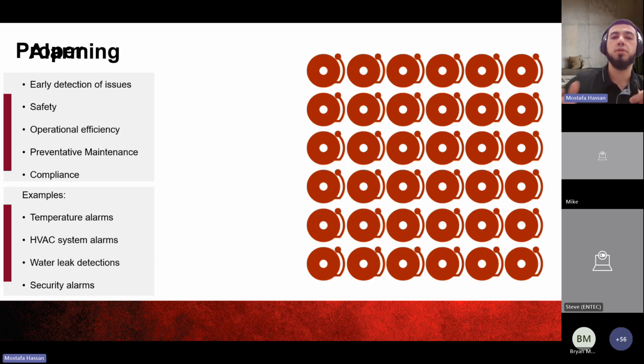And last but not least, while you're specifying, while you're thinking about these alarms, you want proper alarming. You don't want just repetitive alarms bugging you, right? Or redundant alarms that don't make any sense. Think of that trend log example with the chiller. Imagine that chilled water valve every time it switches position and asks for 100% chilled water. That should probably be an alarm, right? And I know the valves are rated for 100% open, but you shouldn't need the valves to be 100% open all the time. Right, so that should probably be an alarm.